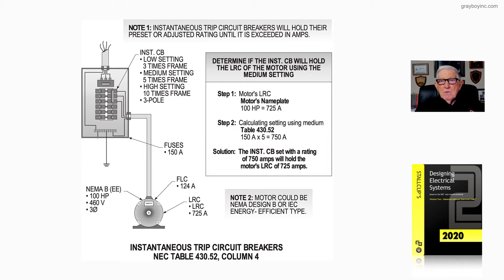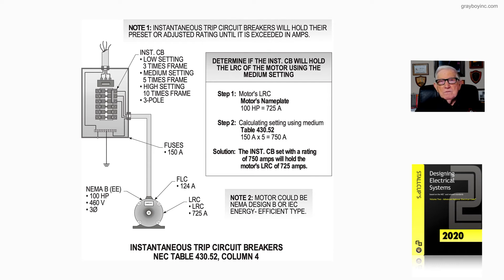Remember you can always go to the table of contents to find Article 430. Find the part that deals with what you're trying to do — if you're sizing conductors, that's Part Two, and go to Part Two of Article 430. It even gives you the page number. You scroll down until you hit 430.22. If you're sizing the overcurrent device, go to the part that deals with sizing the overcurrent protective device.